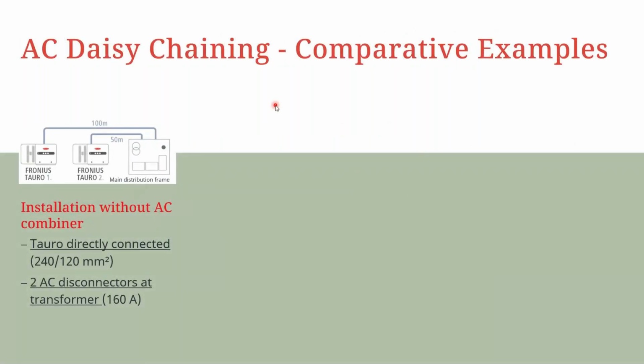So going forward, let's put it in a bit of perspective. Let's see how cost effective this becomes in the practical case. Let's have this scenario of two Fronius Tauro inverters installed. One is 100 meters away from the main distribution frame, while the other one is 50 meters from the distribution frame. If the AC cable is going to be laid, of course, you're going to have a total cable length of 150 meters. Now, you would also have to ensure that you have AC disconnectors, respectively, of 160 amps that will be able to accommodate the load current, obviously. So that's the first scenario.